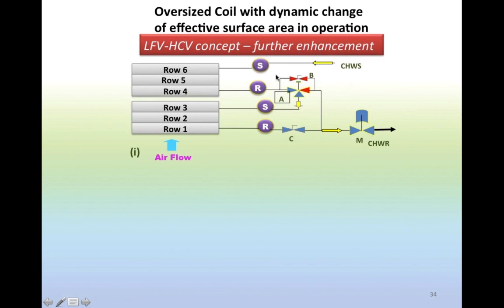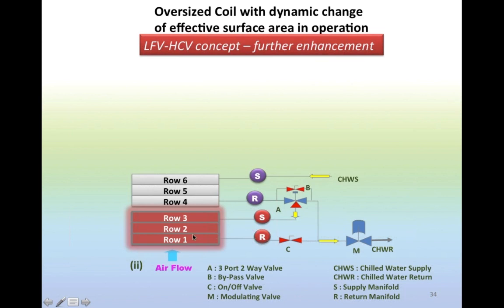See, everything is the same as you would see in a typical conventional design, supply and return, but with this modification here. What's going to happen is if I have my design load as I actually designed for, this should work. And I'm doing exactly what a typical consultant's design would be. Now at part load, the problem is the coil is oversized. What I can do is, how do I make this large coil become smaller? And this is where my manipulation of the chill water circuiting allows me to do exactly that. Notice what's happening. I have effectively rendered row 1, 2, and 3 inactive.